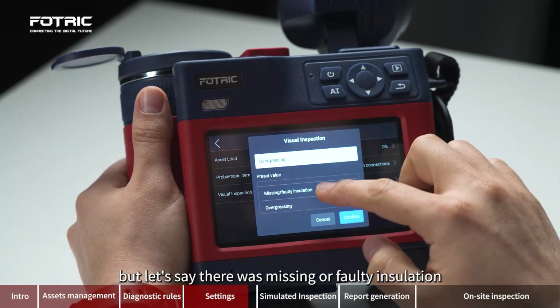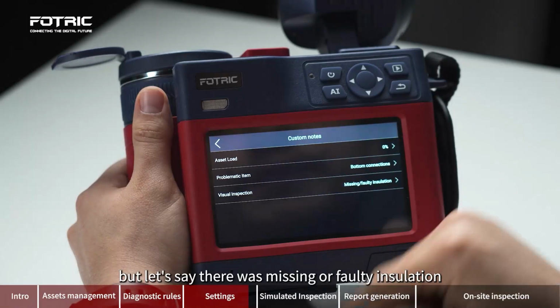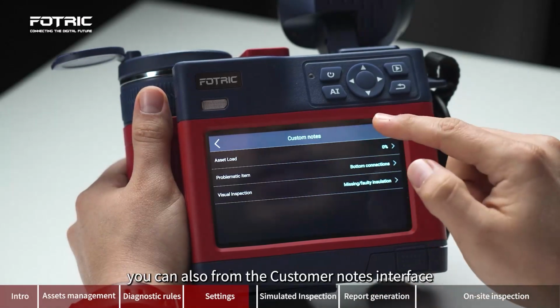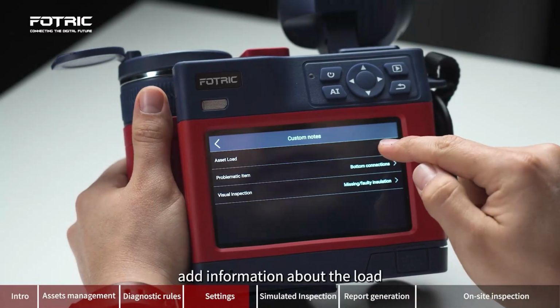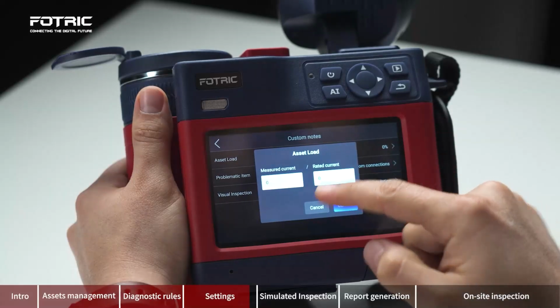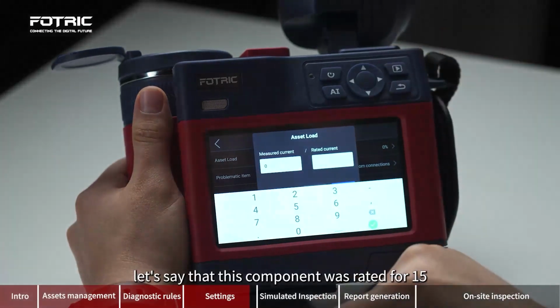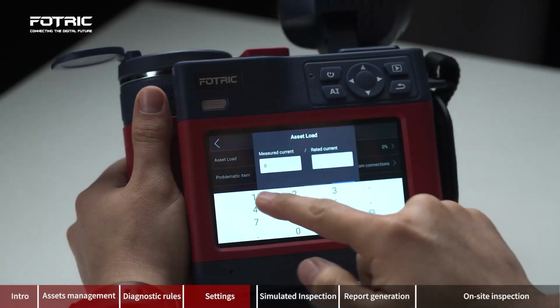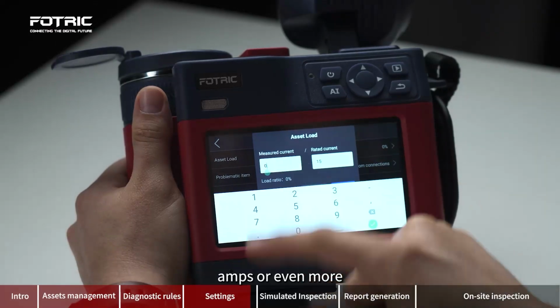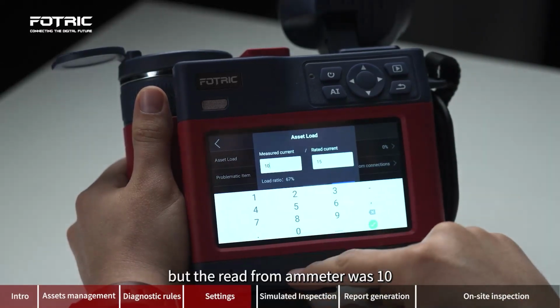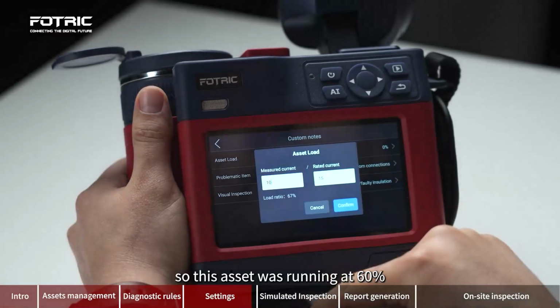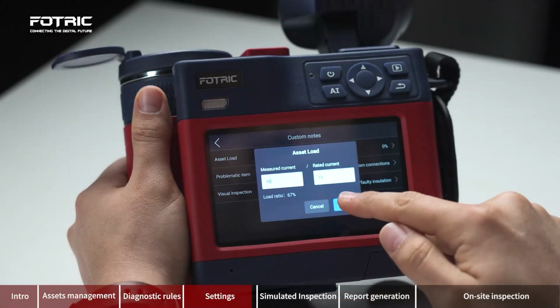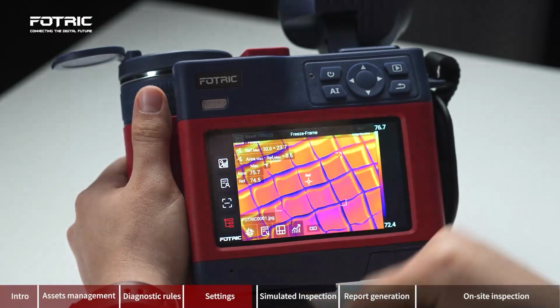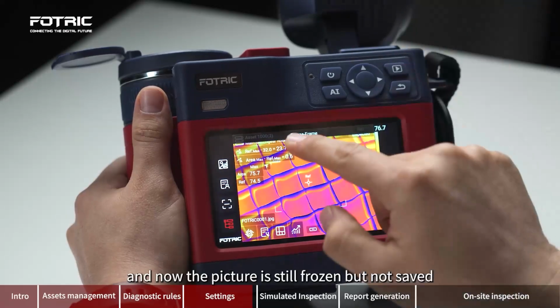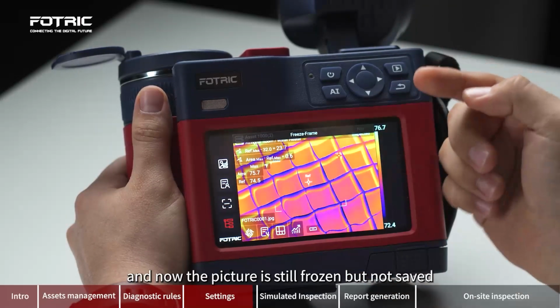But let's say there was missing or faulty insulation. You can also, from the custom notes interface, add information about the load. Let's say that this component was rated for 15 amps or even more, but the reading from the ammeter was 10. So this asset was running at 67% load. Confirm.